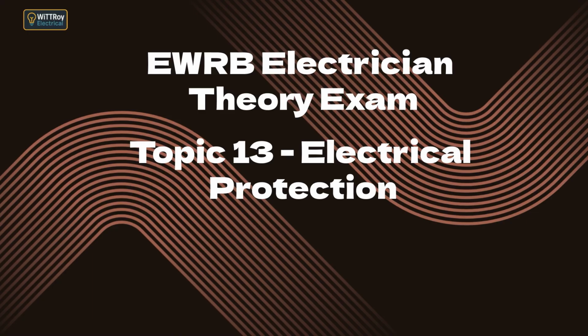13.1c: state forms of excess current protection: close excess current protection and coarse excess current protection. There are two forms of excess current protection, close and coarse. Close excess current protection is the more sensitive type. It will operate within 4 hours when the current reaches 1.5 times the designed load current of the circuit. This means the protective device responds sooner when the current is above normal levels. Close protection is found in modern protective devices such as MCBs and HRC fuses.